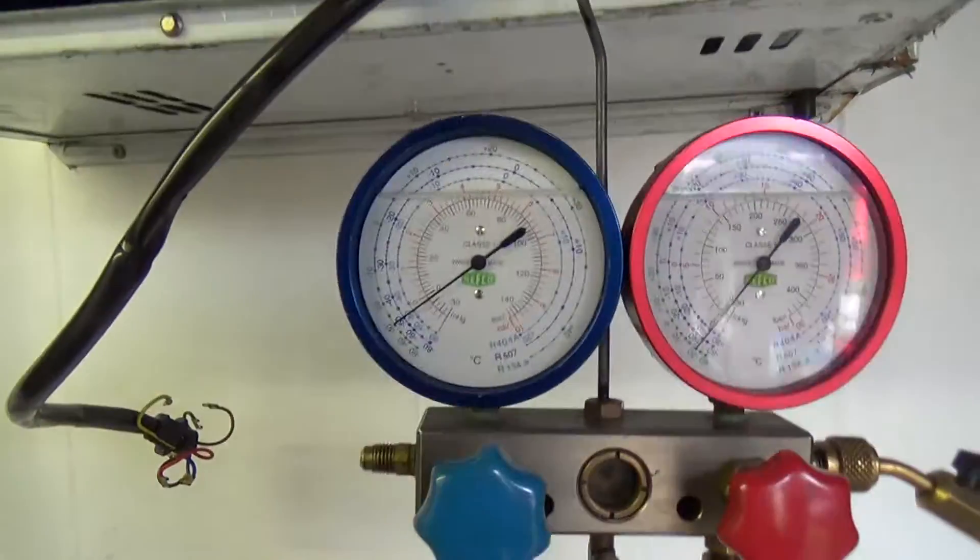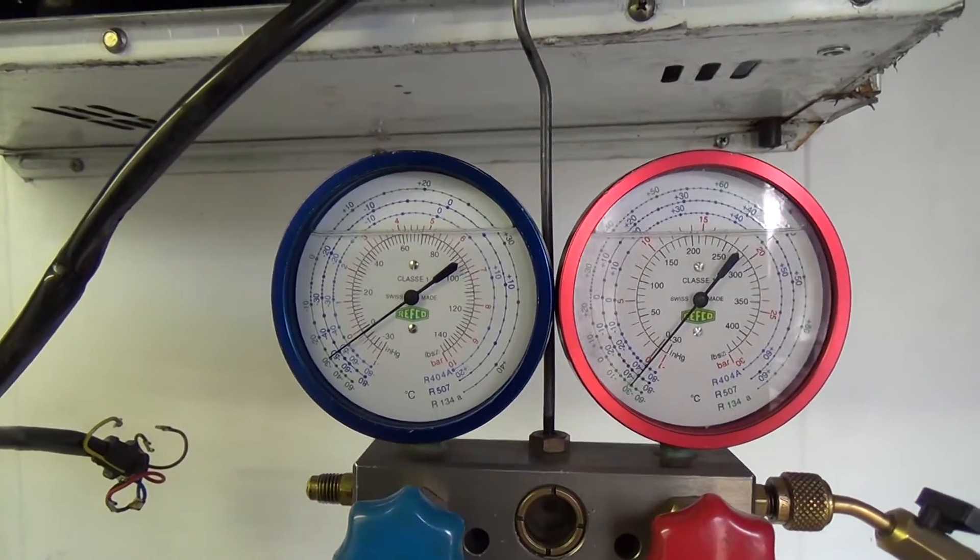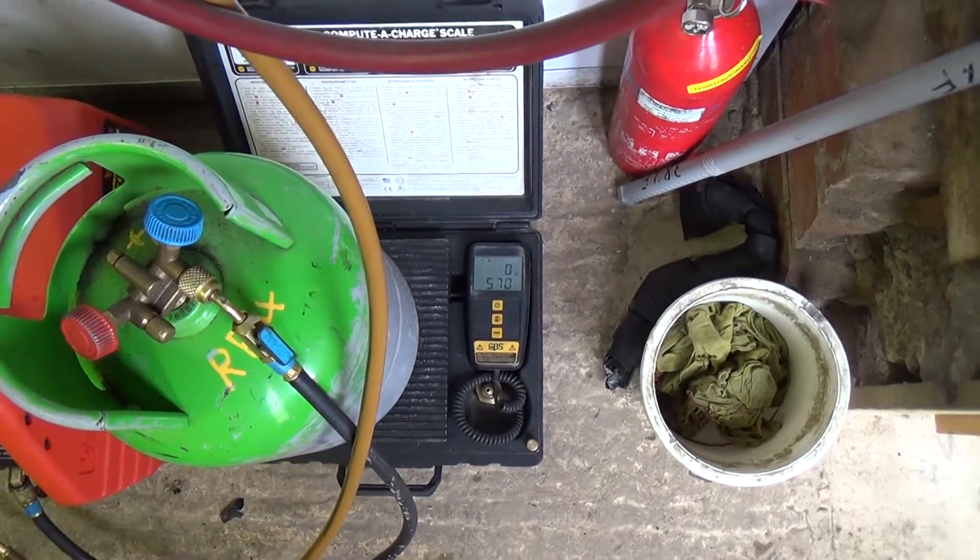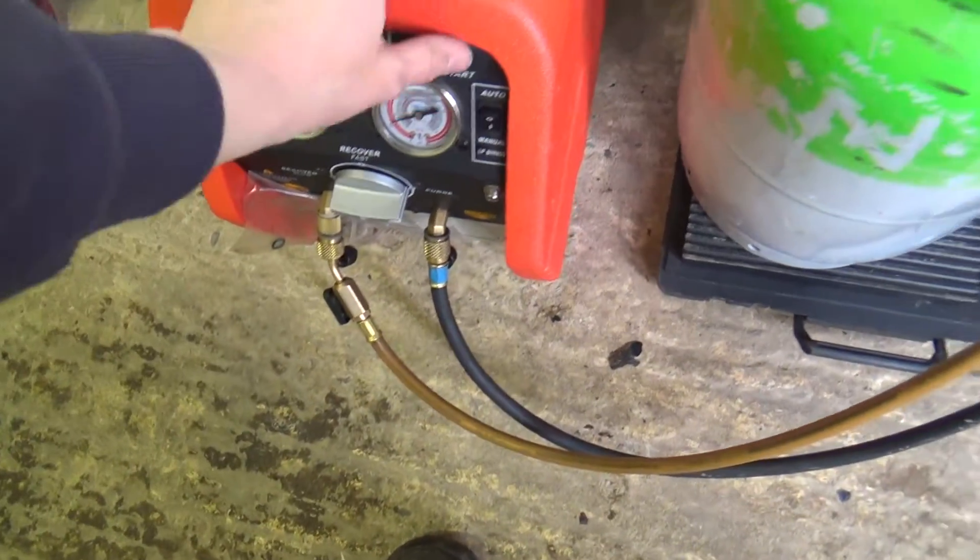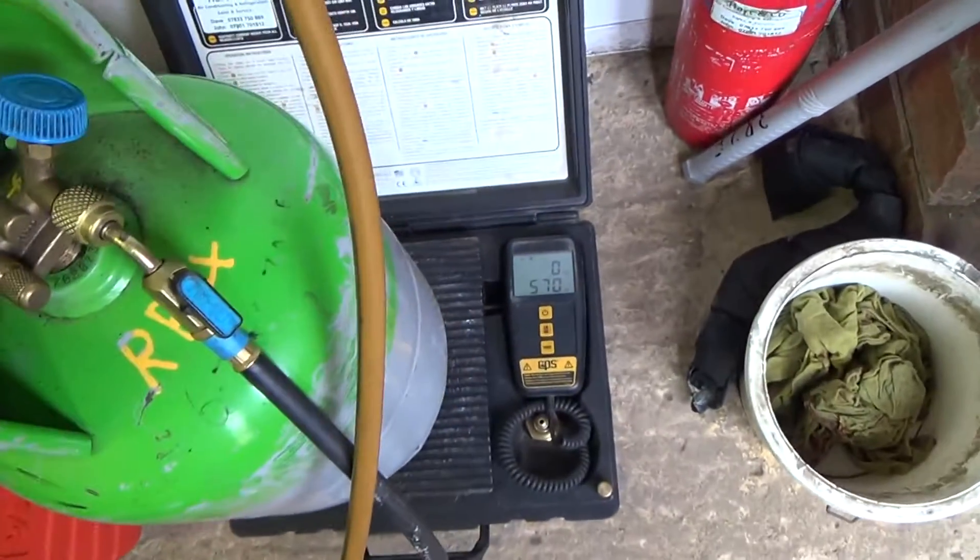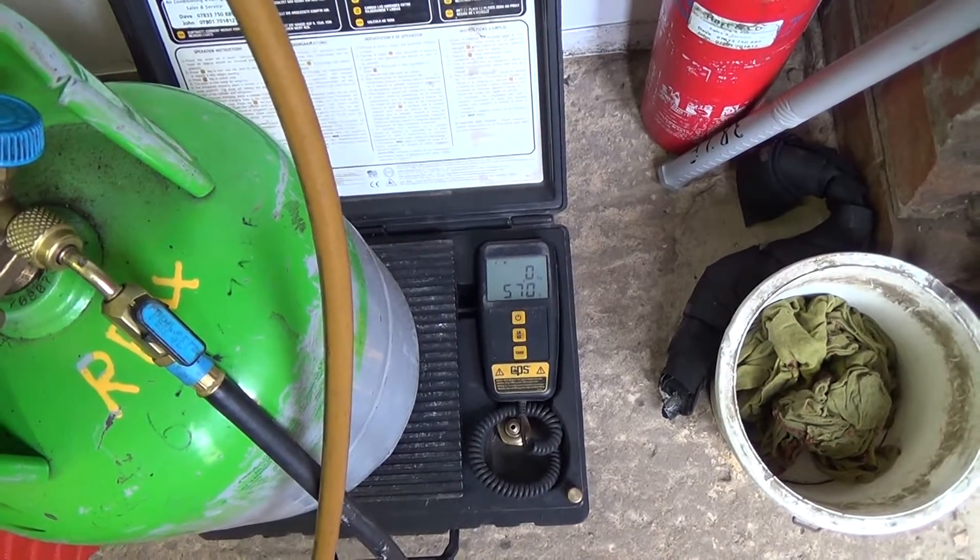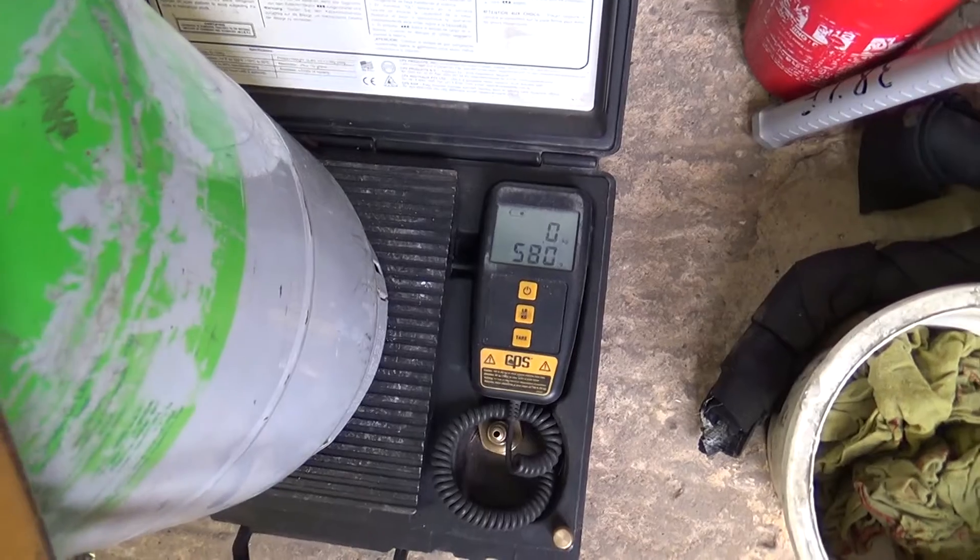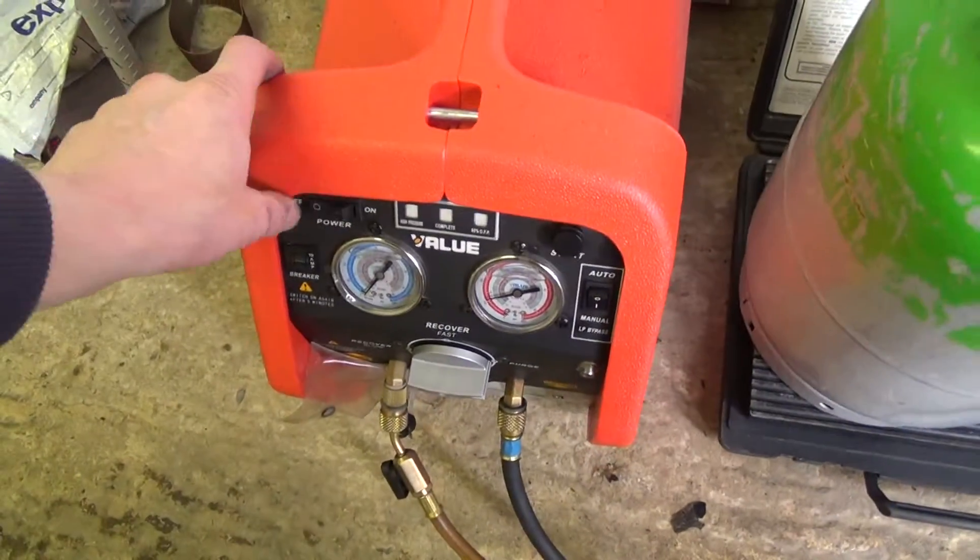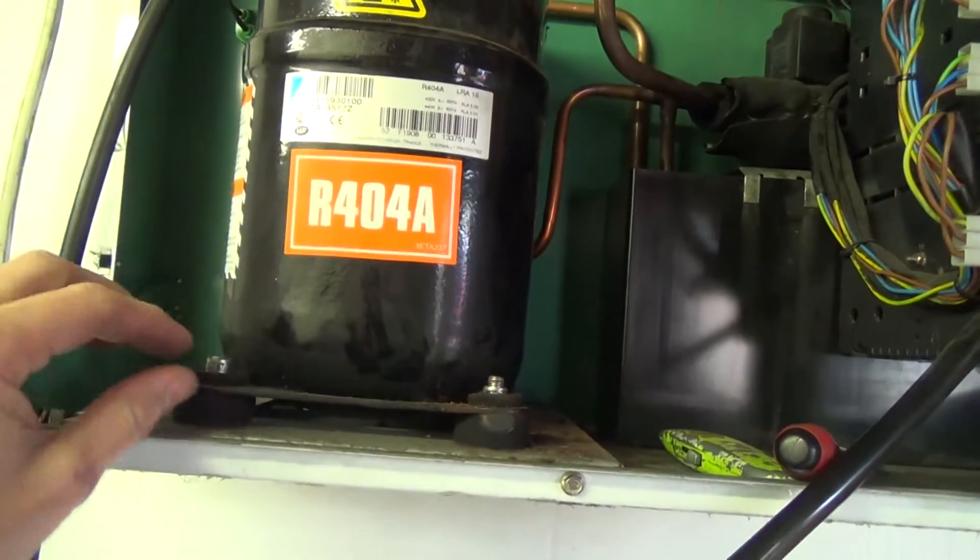Right, we've got it flipped into a vacuum. It's quite cold today so it's still boiling off out of the oil. You can see it bubbling away. We've got about 550, 570. It's probably a bit in the machine as well. Let's put that on the purge. Let's see what we can get out of it. Not much. There might be another 100 grams in there.